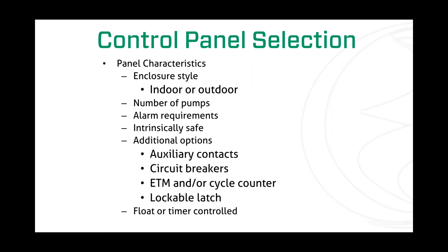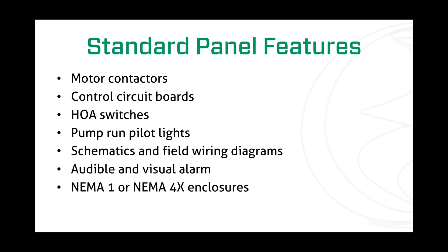I want to talk about some of the standard features of Zoeller's standard line of control panels. These panels typically contain features such as a motor contactor, a circuit board, and a HOA switch—or hand-off-auto switch or switches. They'll probably have a pump run light, and they'll definitely have schematics and field wiring diagrams. They probably have an audible and visual alarm. These panels are available in both NEMA 1 for indoor locations and NEMA 4X for outdoor locations.